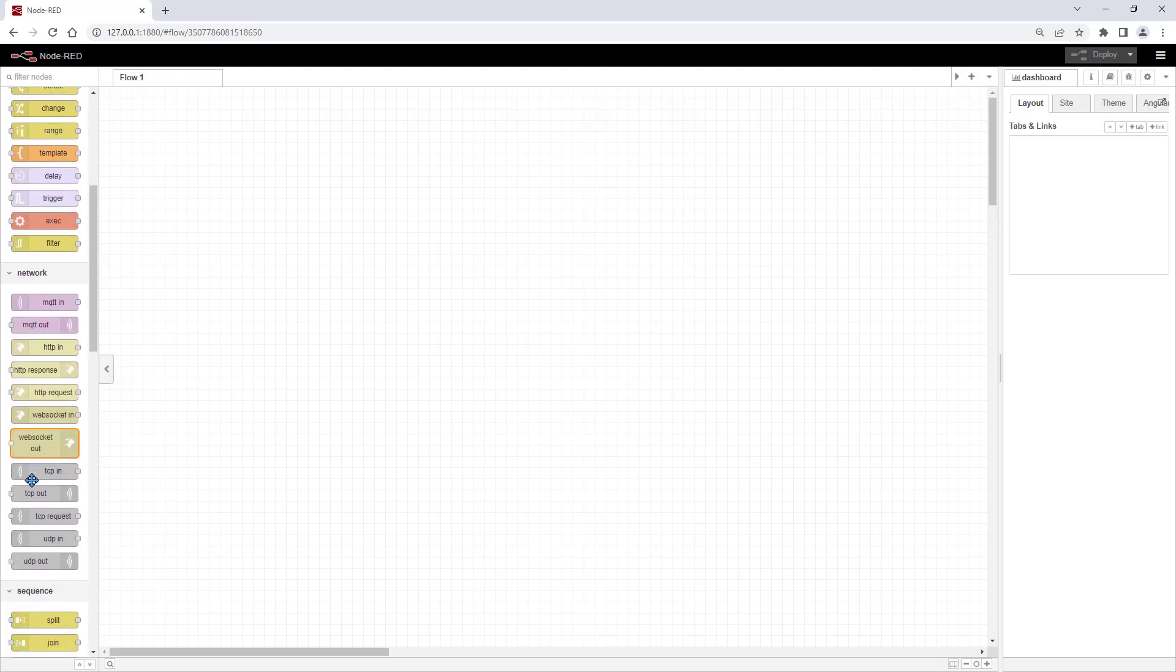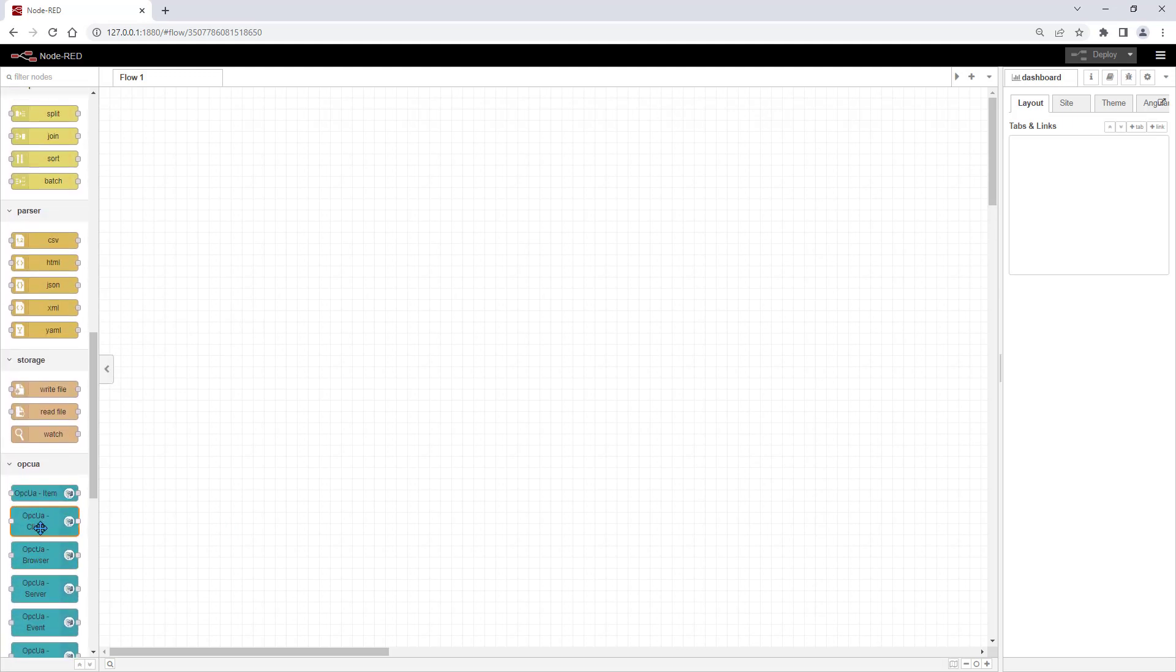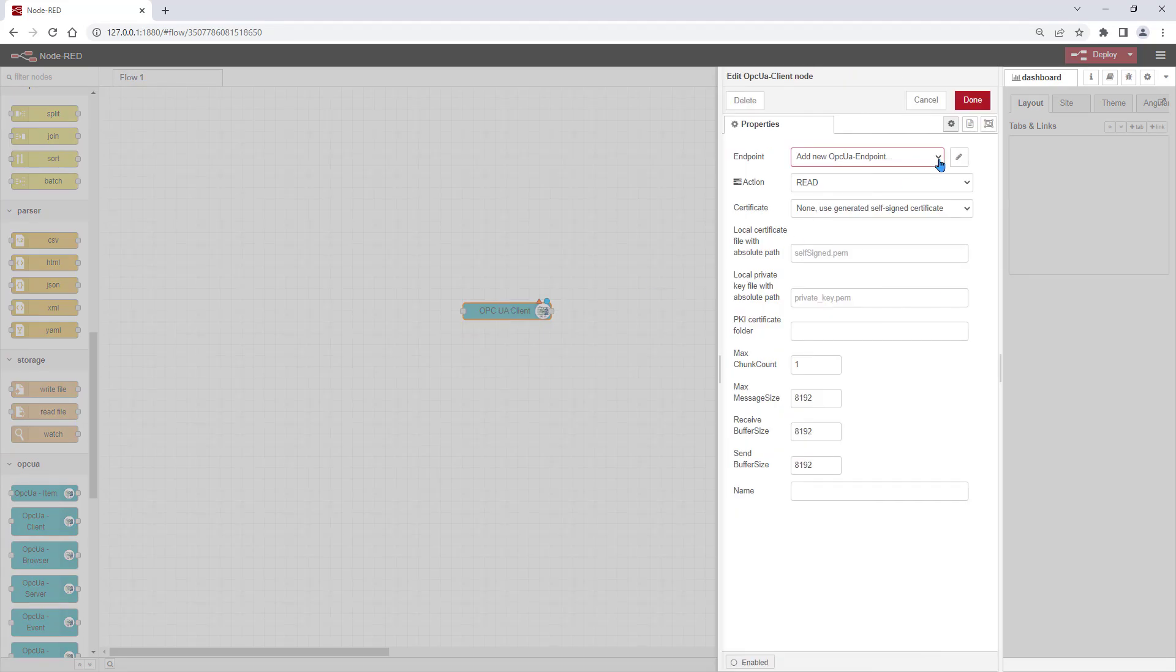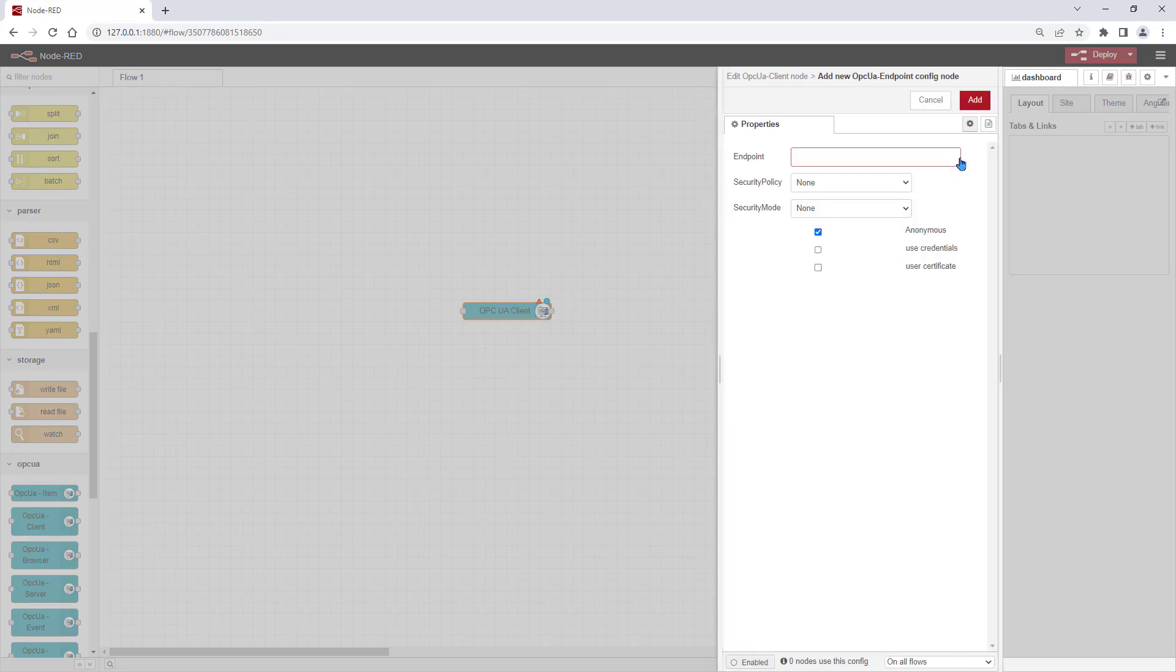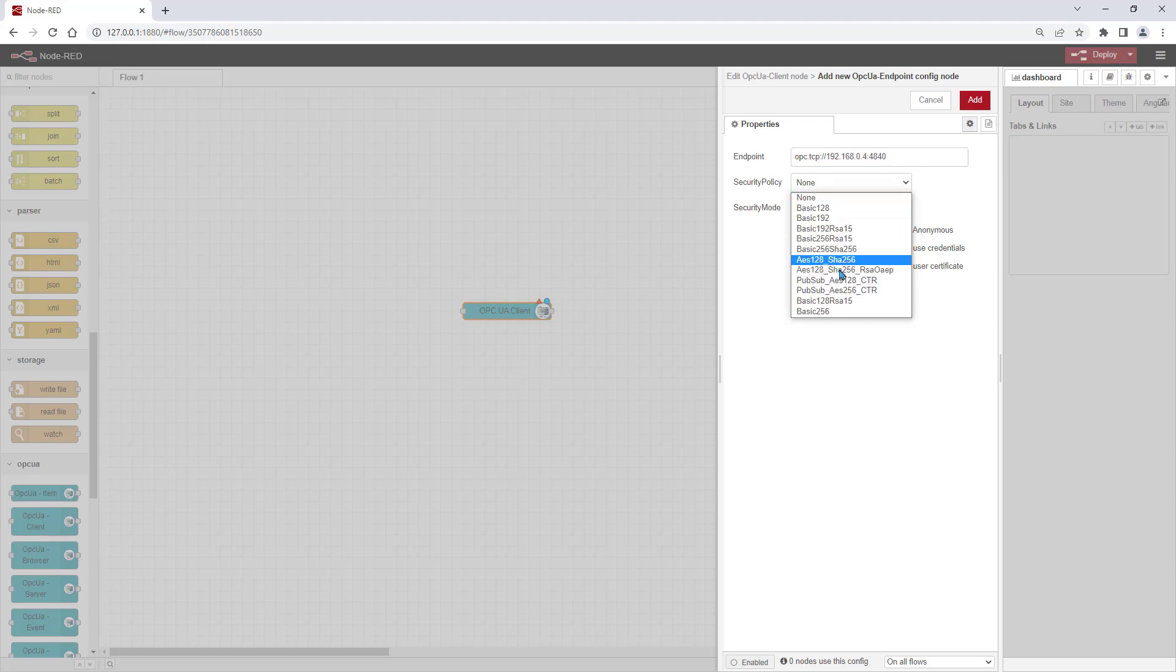We pick an OPC UA client node from the list and place it to our flow. At this node, we configure the SimoCode Pro OPC UA server as the endpoint. For reading access, security policy and security mode can be kept as none.